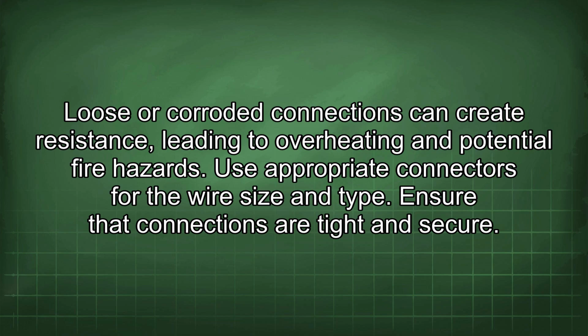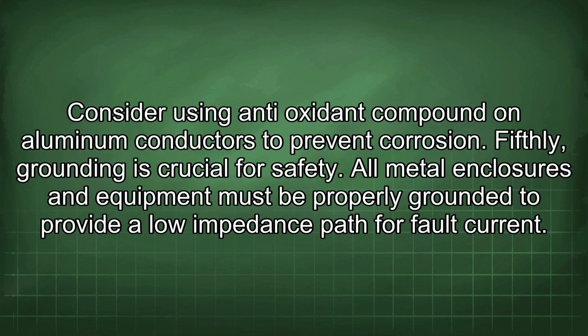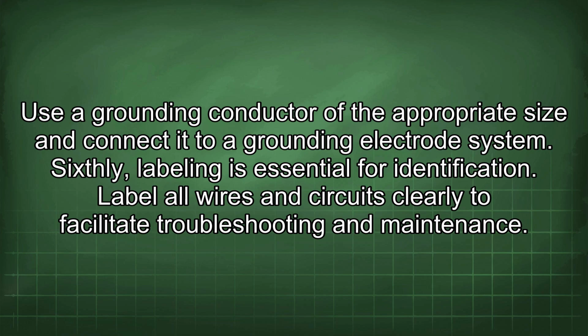Use appropriate connectors for the wire size and type. Ensure that connections are tight and secure. Consider using antioxidant compound on aluminum conductors to prevent corrosion. Fifthly, grounding is crucial for safety. All metal enclosures and equipment must be properly grounded to provide a low impedance path for fault current. Use a grounding conductor of the appropriate size and connect it to a grounding electrode system.